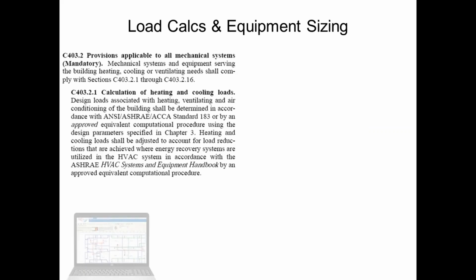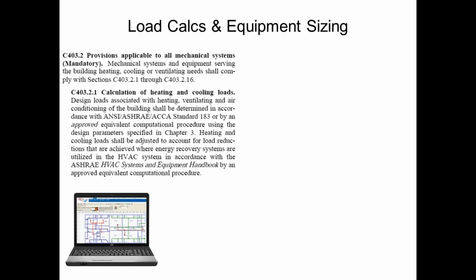So first thing is calculations for loads and equipment sizing. Just like with all systems on a rooftop project, you need to do a load calculation. That is required by code. It's been required for a while. Some areas enforce it more aggressively than others. This is a statewide code, but in Illinois, codes are enforced at the municipal level. So some cities are more aggressive than others in terms of policing the code. By the way, I should mention that even if your town doesn't police the code, or even if your town doesn't even have an inspector for that matter, you still have to comply with the state code. It's not an optional thing. It's not a municipality telling you you have to do it. It's a statewide code, so it's essentially the law everywhere. So even if you're not getting flagged by an inspector, you still got to do this stuff.